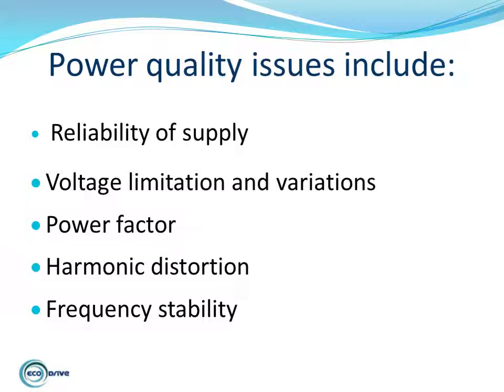In 2011, an article appeared in the Courier Mail flagging that the grid system transformers in the Sunshine Coast region had reached saturation and there was no further capacity to cater for additional grid-connected systems. Grid-connected PV systems that push energy onto the grid cause a slight rise in voltage. Where the impedance connecting the system to the grid is high, the voltage rise will be greater.